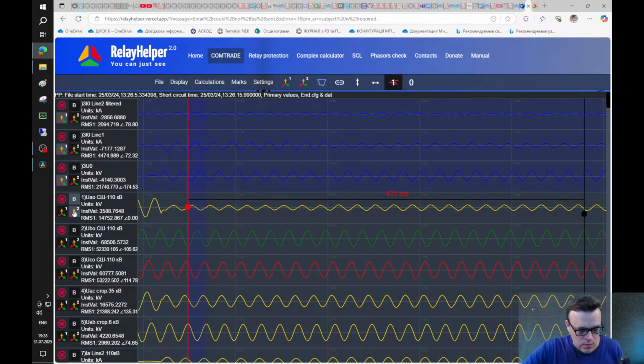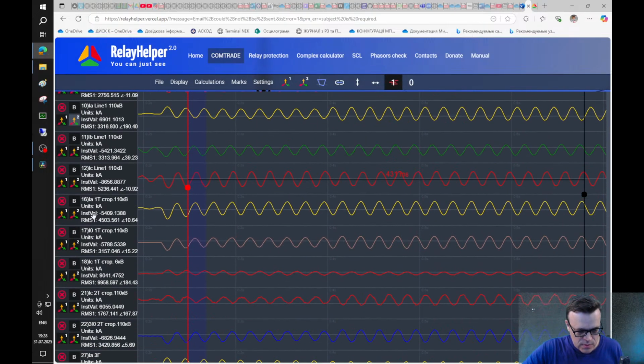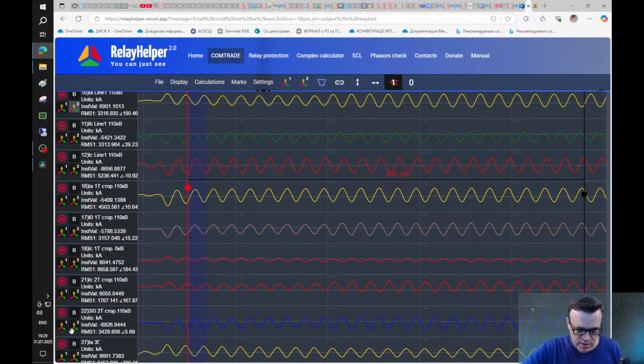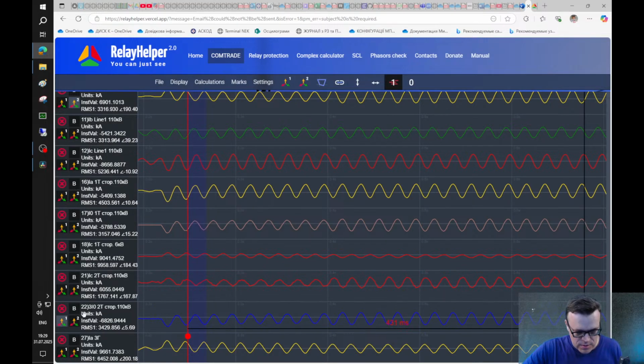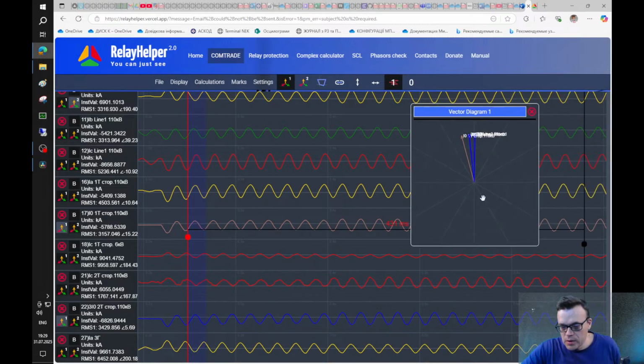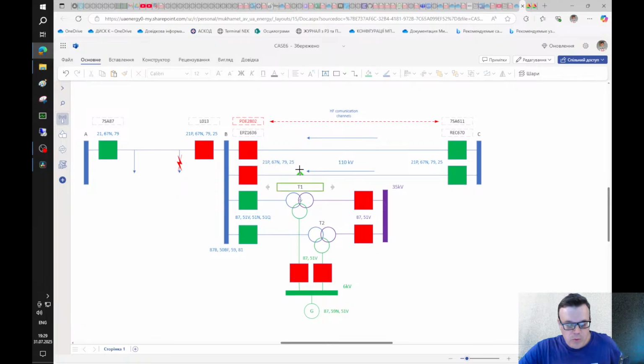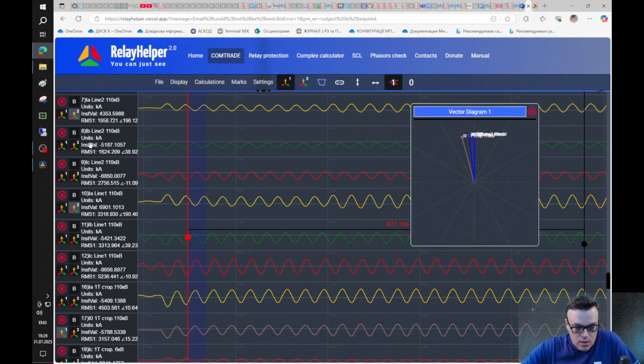I want to add all zero sequence currents to see directions of them. This is transformer 2, this is transformer 1. Okay, we can see that they are directed the same. So I can make a sum of them, and with this sum I receive a zero sequence current that flows during the event on this particular circuit breaker, and what protection should measure.